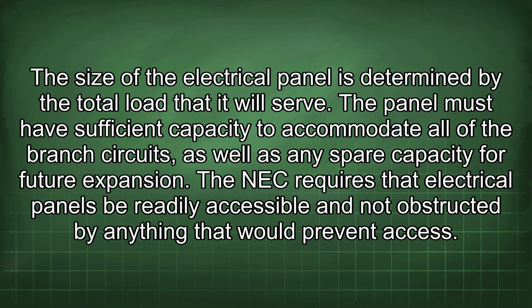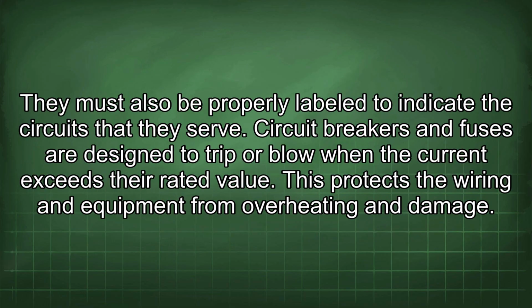The size of the electrical panel is determined by the total load that it will serve. The panel must have sufficient capacity to accommodate all of the branch circuits, as well as any spare capacity for future expansion. The NEC requires that electrical panels be readily accessible and not obstructed by anything that would prevent access. They must also be properly labeled to indicate the circuits that they serve.